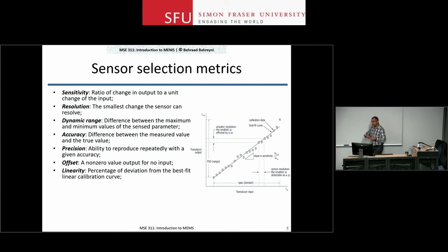Linearity is, you know, how well those measurements for different input amplitudes lie on a straight line, right? And then any deviation from a straight line in terms of input-output characteristic curve will be an issue of nonlinearity. Drift is how stable the sensor output is over time.